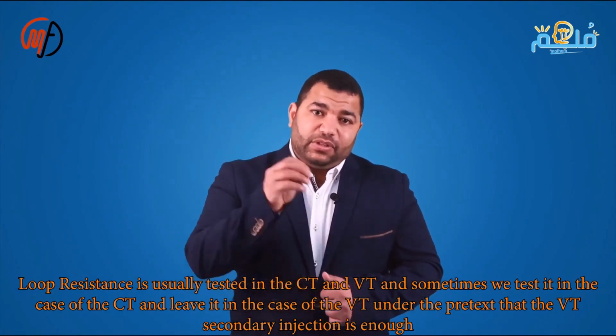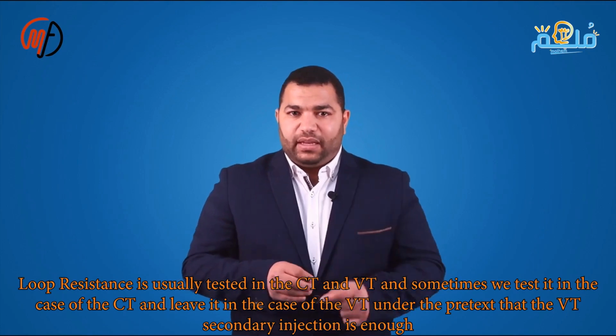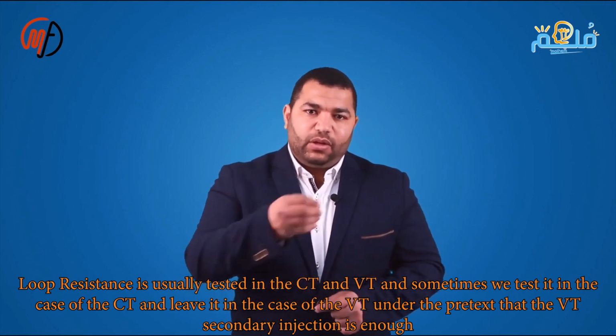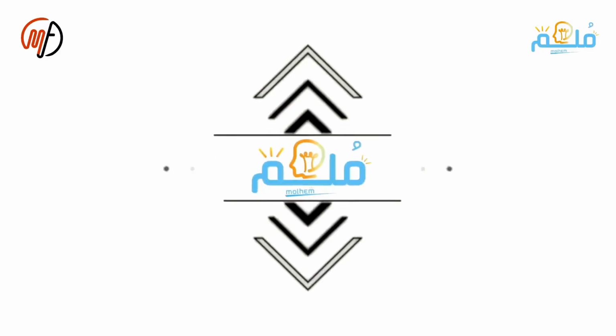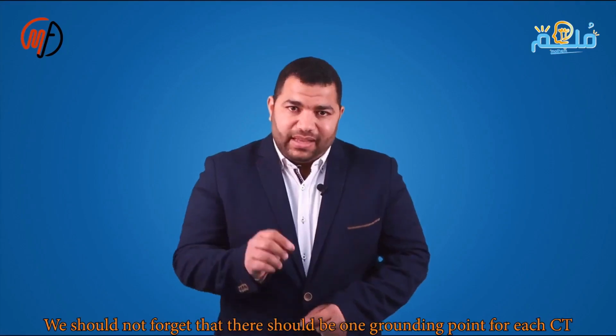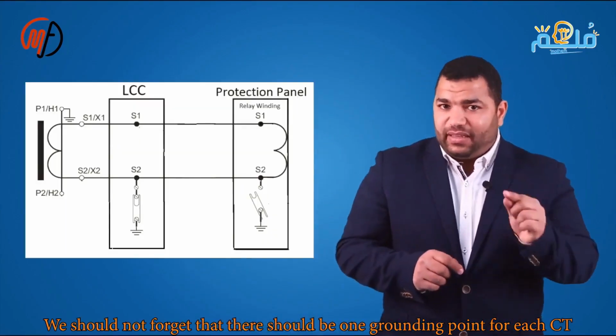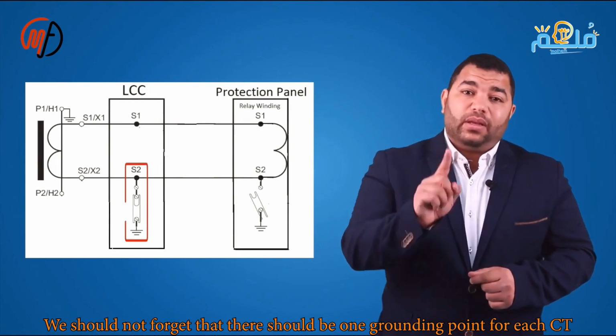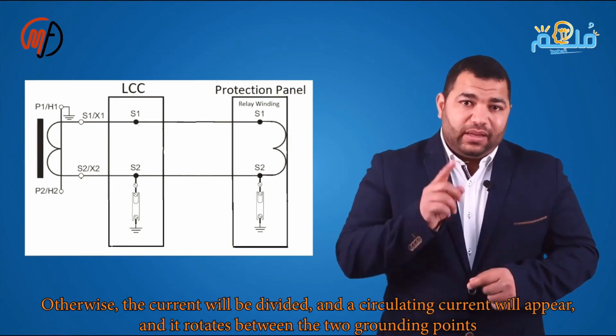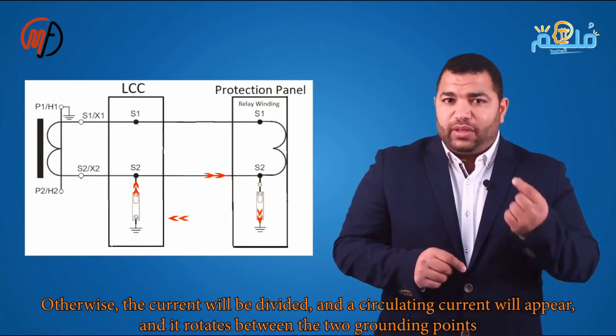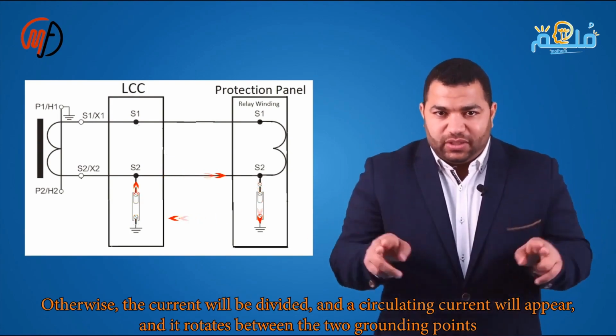Connect the CT's secondary to ground. Buzzing means closed grounding. If buzzing persists after opening the terminal, another ground exists. And do not forget to test the single earthing point of the CT, so that there must be one earthing point for each CT loop. Otherwise, the current will be divided and there will be what is called circulating current between the 2 earthing points.